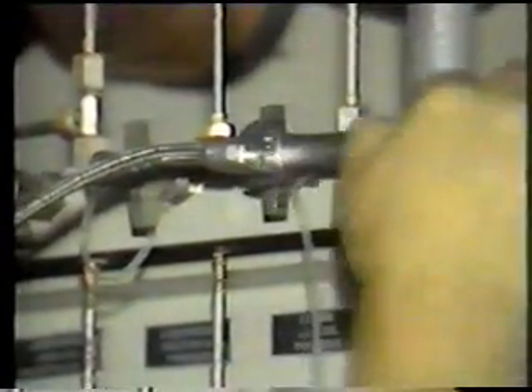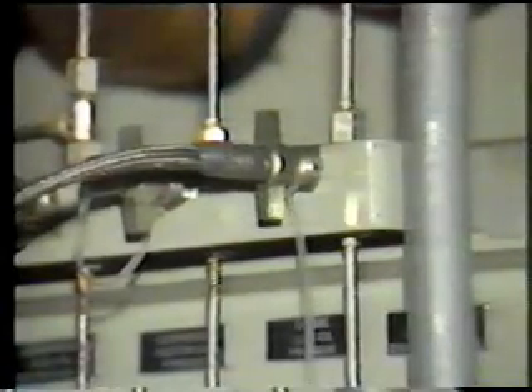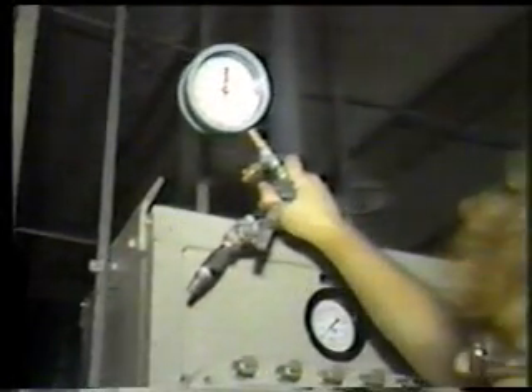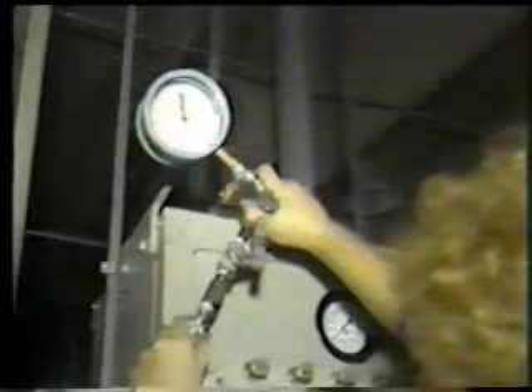Next, connect the hose from the master test gauge to the test connection on the manual shut-off bleed and instrumentation valve. Be sure all connections on the master test gauge assembly have been tightened. Then place the assembly on top of the panel so that it can be reached from the front. Now, at the front of the panel, connect the external pressure source to the master test gauge assembly.